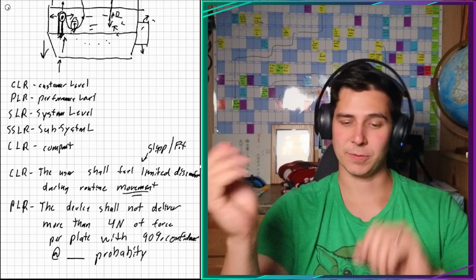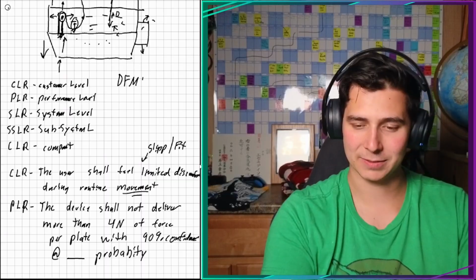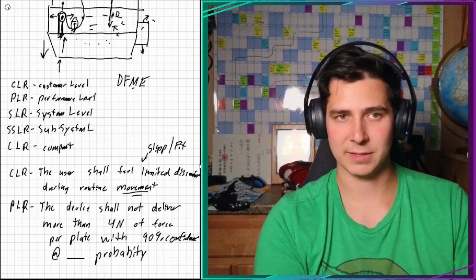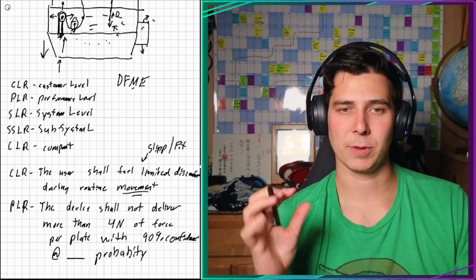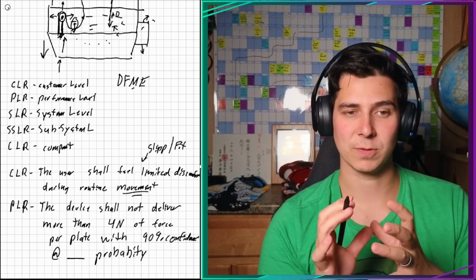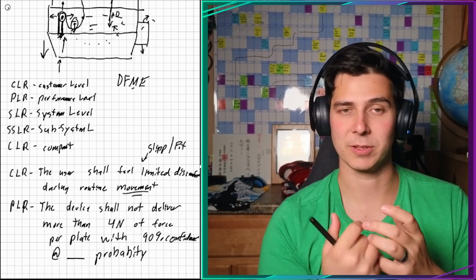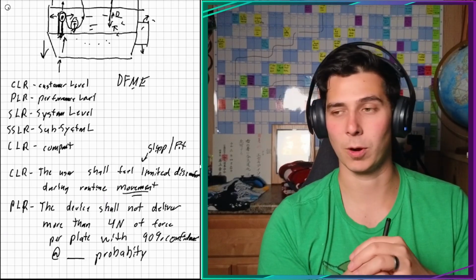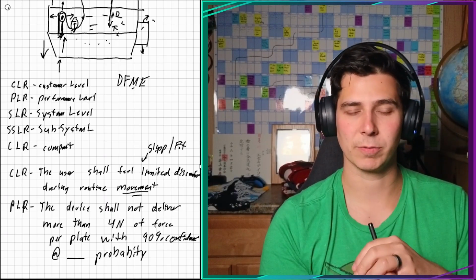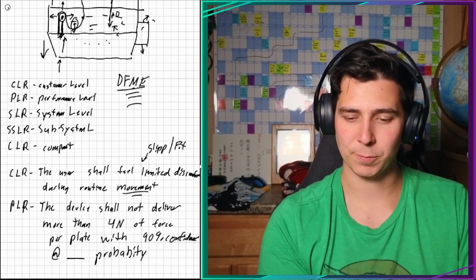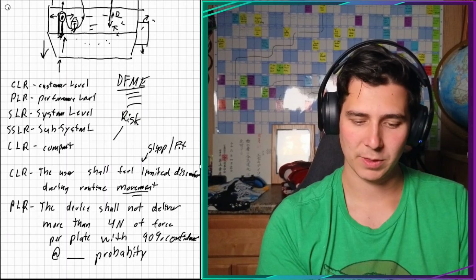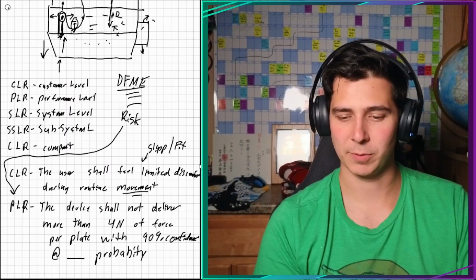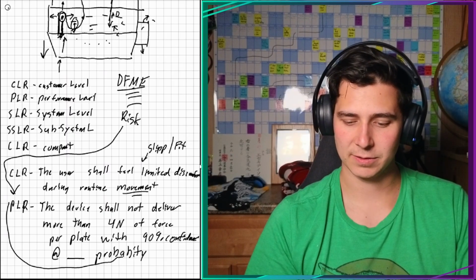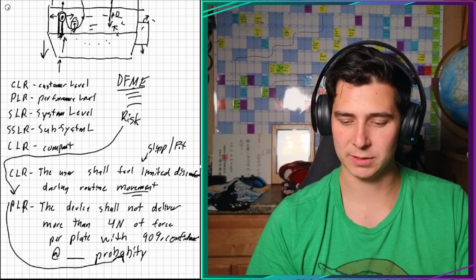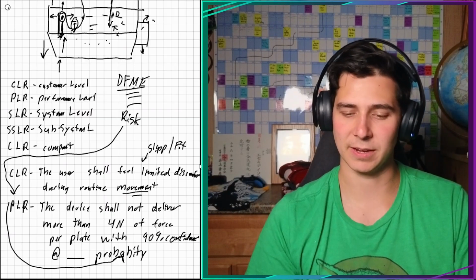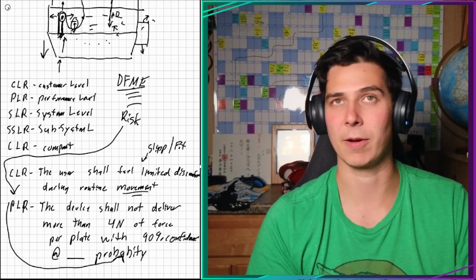So there's a risk. If you had a DFMEA, design failure modes and effects analysis, you might have a failure mode where this provides too much force that causes the patient to experience some kind of bruising or pain or constriction of blood flow to the remnant limb. So the risk in your DFMEA would then drive the PLR, the performance level requirement, and then your quality engineer would help you determine what statistical confidence is necessary based on the risks that could occur and the different outcomes that could come from that.